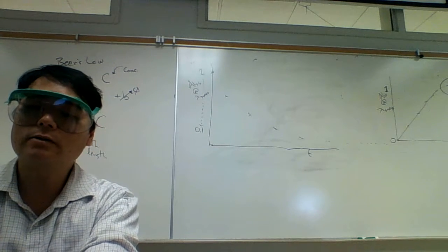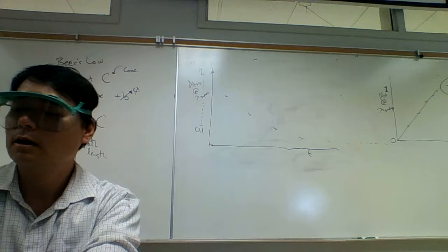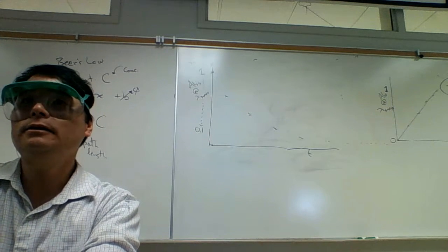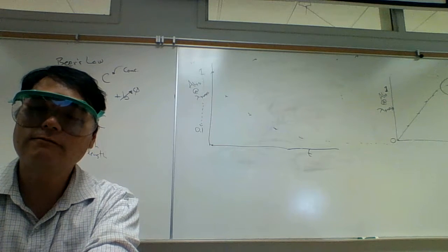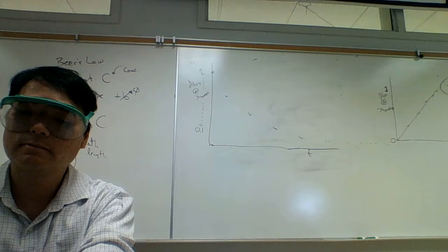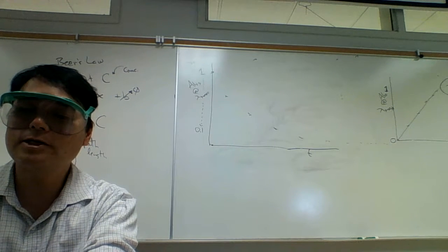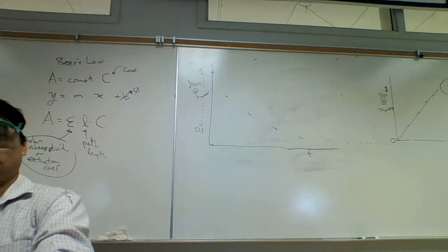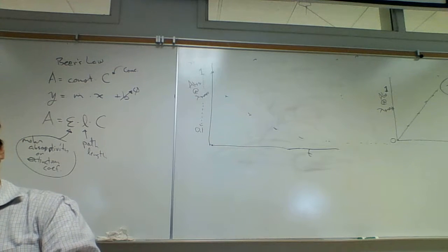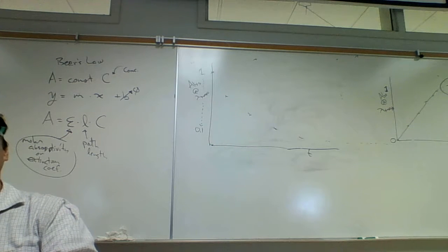Okay. Now, we could skip the warm-up. This has been on continuously. So skip warm-up. Put the blank inside the SpectroViz. And then finish the calibration. Calibration complete. Click OK. All right, now we're ready. With the blank in there, you should be getting an absorbance about 0, plus or minus the noise. You know, the small fluctuations.